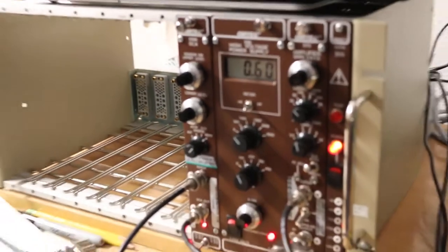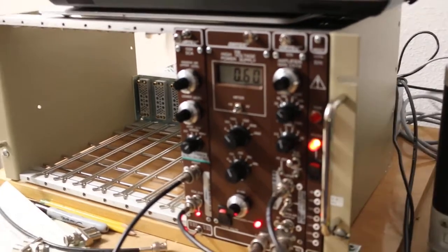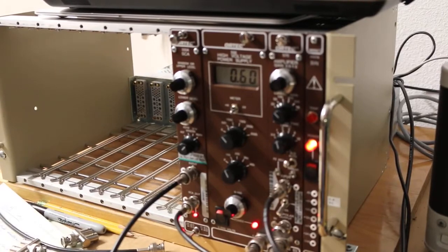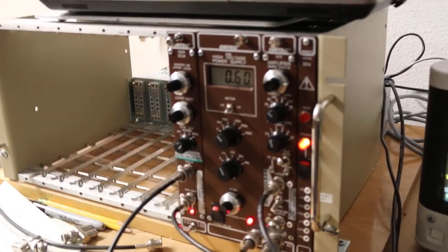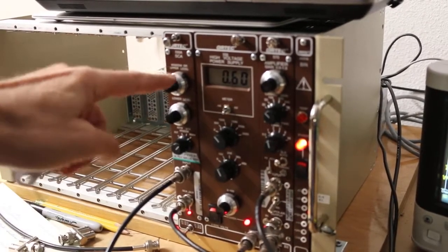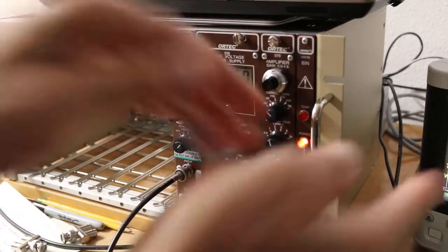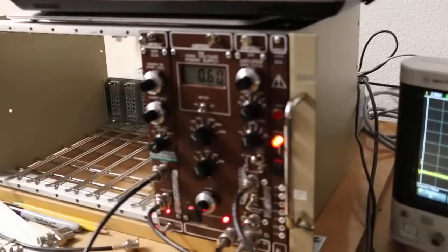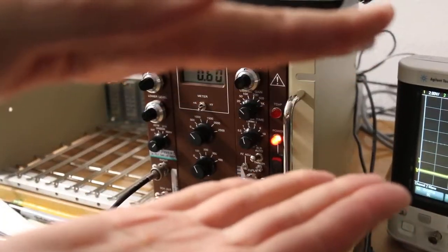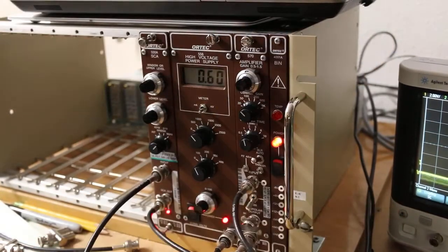Okay, so in the last video we introduced a new NIM module called the SCA, the Single Channel Analyzer. And as we discussed, what the SCA allows you to do with the lower level knob and upper level knob is set a voltage window. And if a voltage pulse comes in like that, and at some point the voltage goes between these two voltage levels, the SCA will react. Now, react isn't a great word, but let me just tell you what react means.